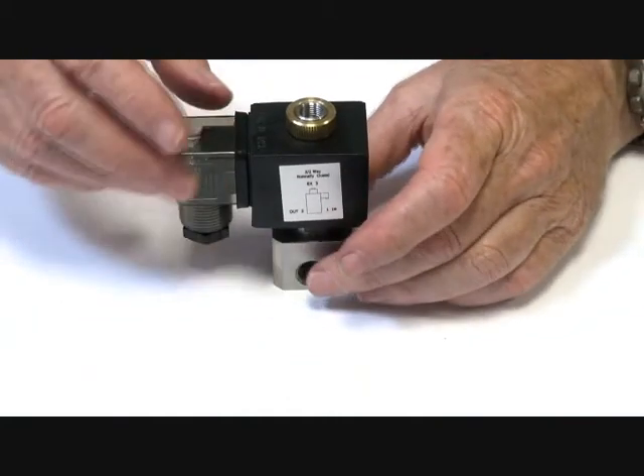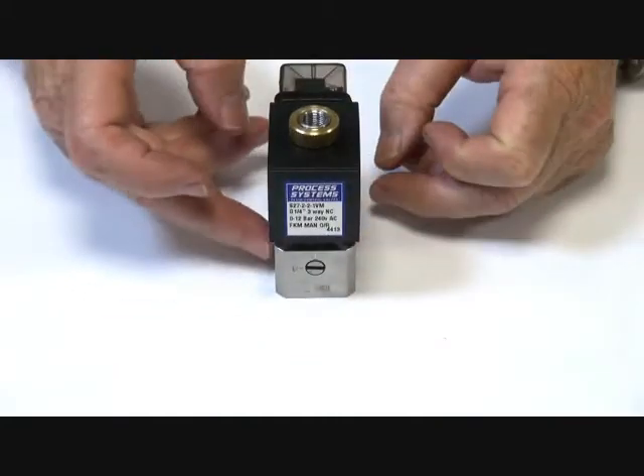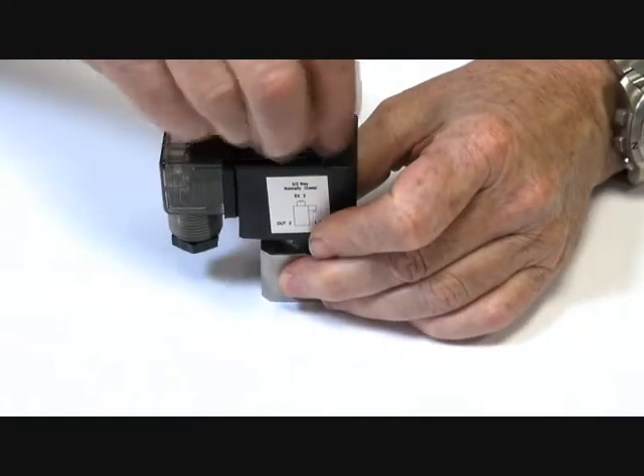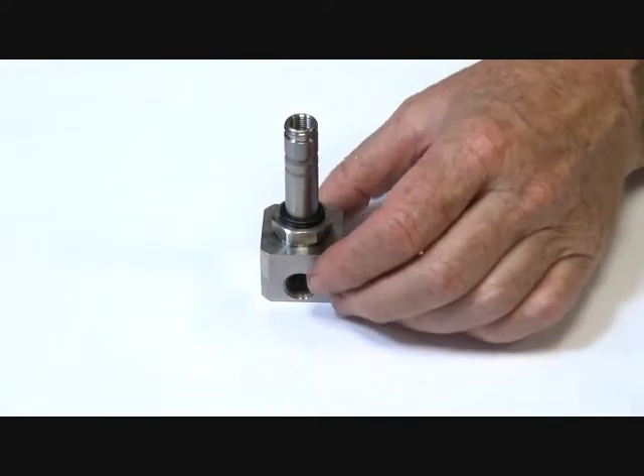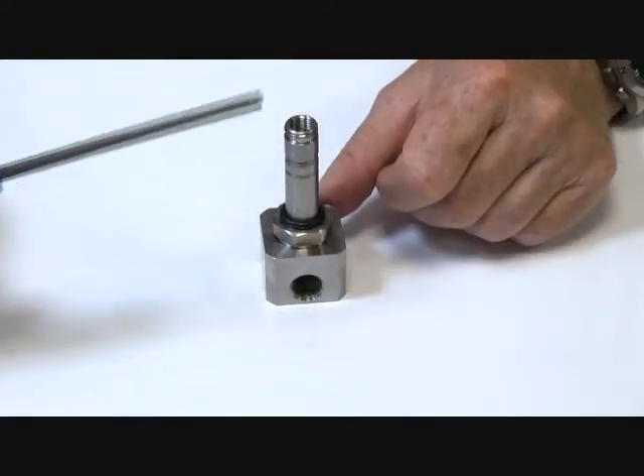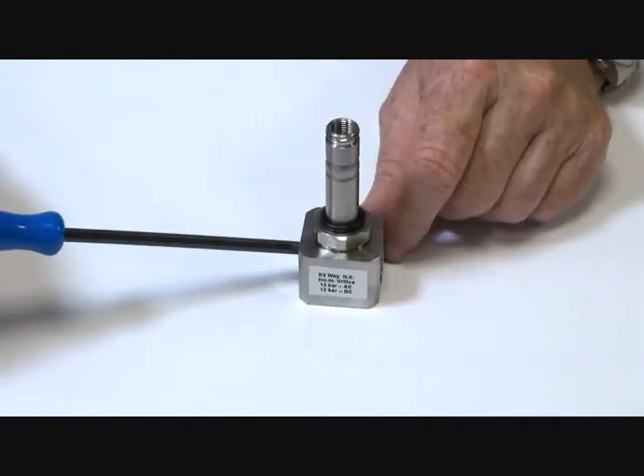Your supply is in port 1, out port 2, and exhaust port 3. When the valve is de-energized, port 2 is connected to the top exhaust, and port 1 is waiting with your main supply.